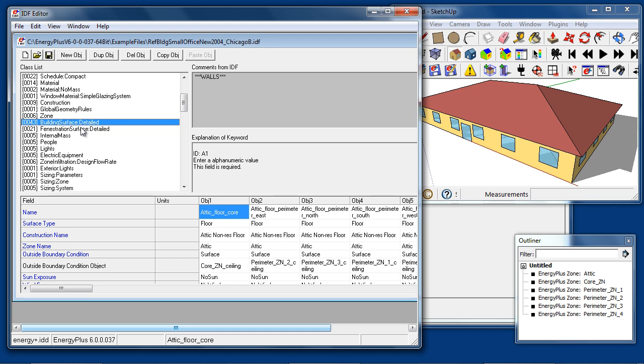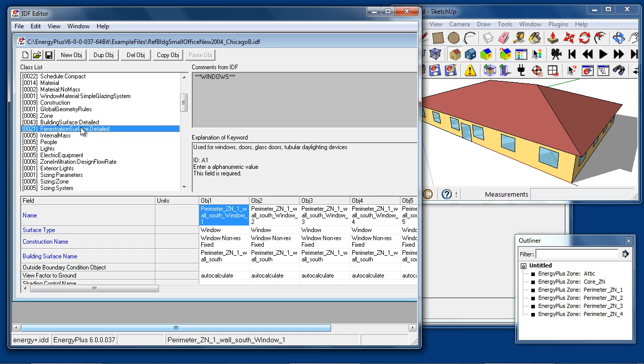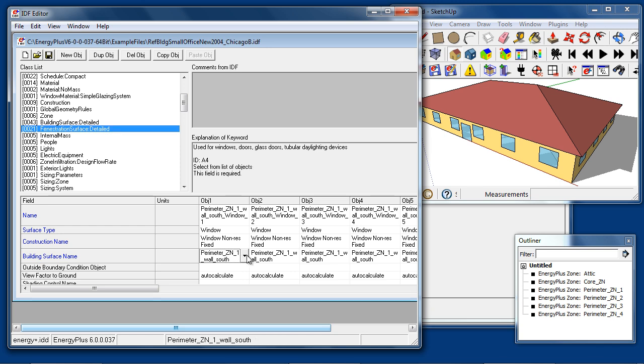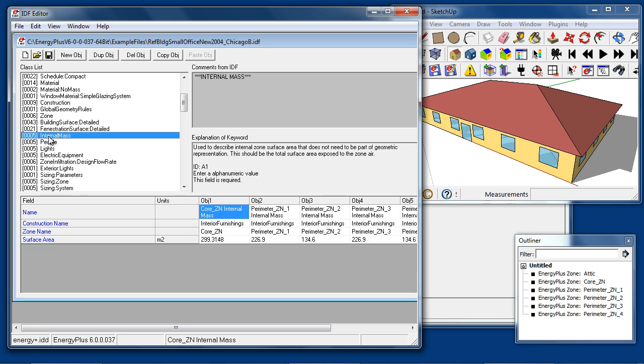Fenestration surfaces are used for windows and doors. They are placed on a base surface. So, a fenestration surface will have a name, a type, a construction name. Then, it will reference a base surface upon which it is placed. This model includes some internal mass objects which add thermal mass to the model without having any specific geometry associated with it.